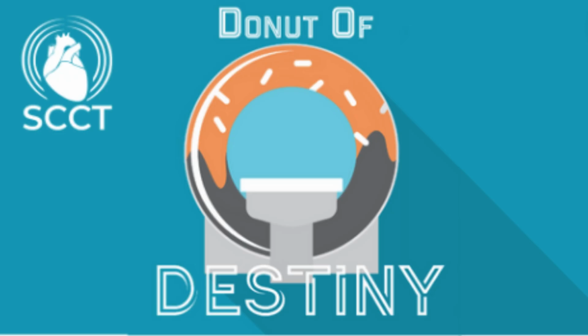You always keep it on so that it maintains its power around its semiconductor and keeps it at operational state. And so that's maybe the one big difference, right? At the end of your shift at 6 p.m., 7 p.m., you don't shut it off and then turn it back on the next morning. You just leave it on. And we continue to work and develop new technologies for low power modes, downtime, and ramping down of the energy consumption so that we are mindful from a sustainability perspective, but we keep the thing on at all times, just like an MR.